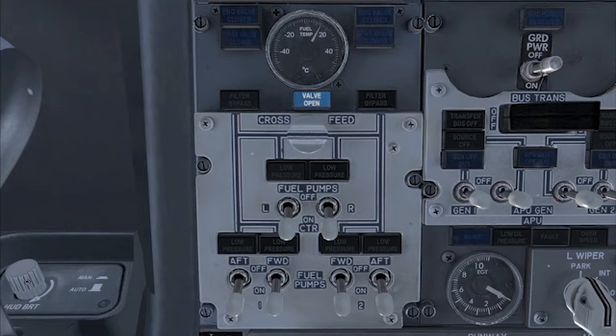Upon moving the knob from open to closed, the reverse occurs. The light goes from dim to bright as the temporary position disagree situation is present. When the valve is returned to the closed position, the light extinguishes completely.